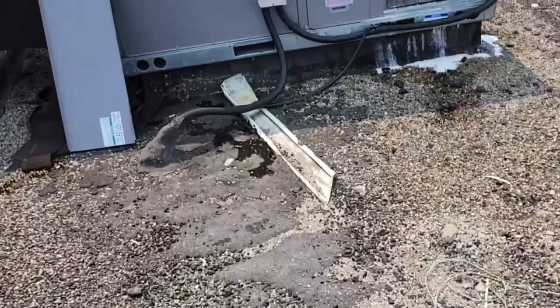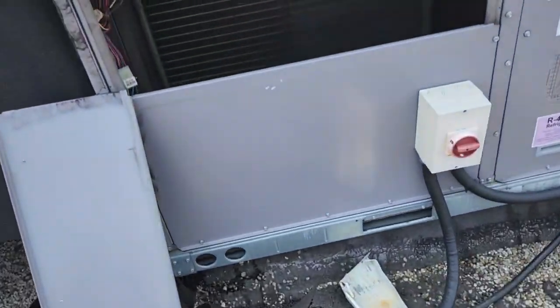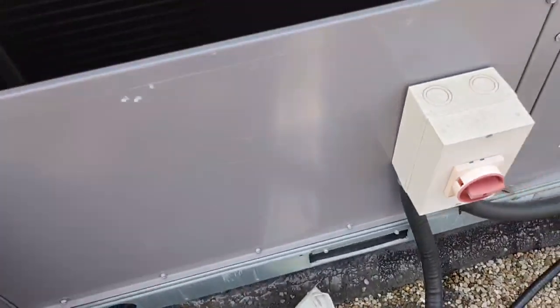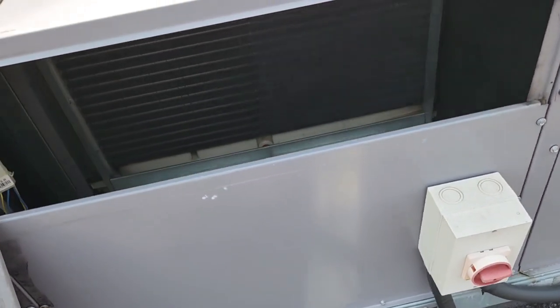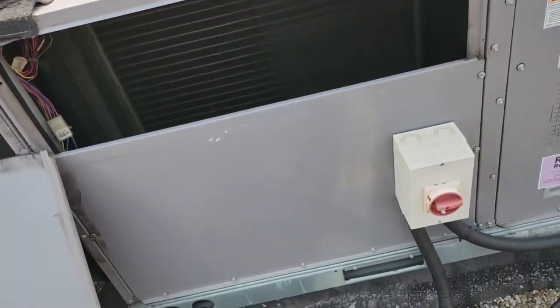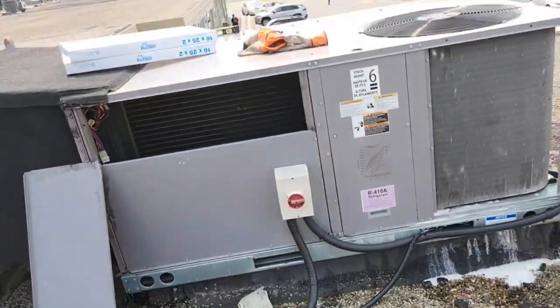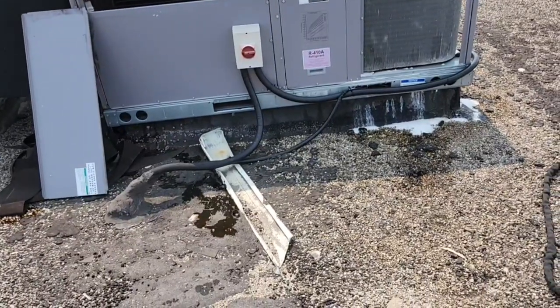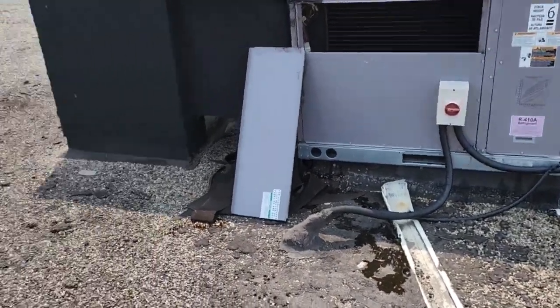That's the evaporator drain. So I guess it's not leaking down there, but this unit should have been installed level. It's really poor installation. Yeah, he left the filters down there too.